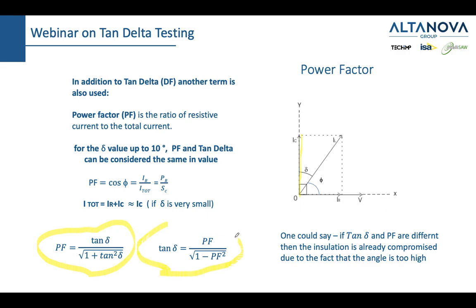And you see, we will say very soon what are the expected values, but let me give you a preview and say that these numbers are very small. Actually, they're very close to, let's say, 0.001 or 0.1. So if you factor that in while looking at this particular formula, you will understand that power factor and tan delta are the same. Actually, for the values of delta, of this angle here, up to 10 degrees, power factor and tan delta can be considered the same value. And one could say that if tan delta and power factor are different, then the insulation is already compromised due to the fact that the angle is too high. So if your delta is more than 10 degrees, we already have too much resistive current, which will in turn then destroy our insulation.